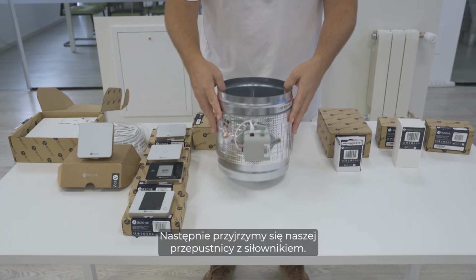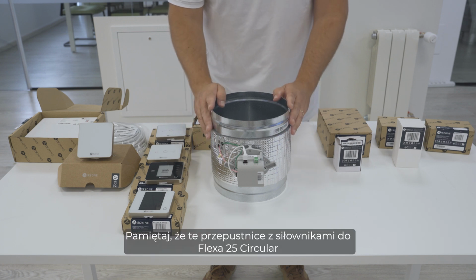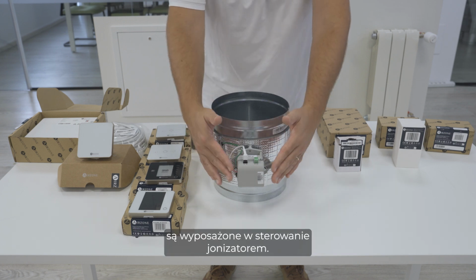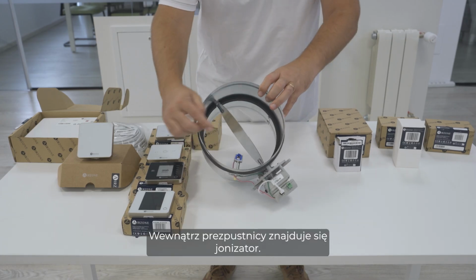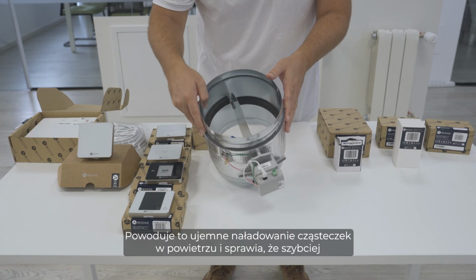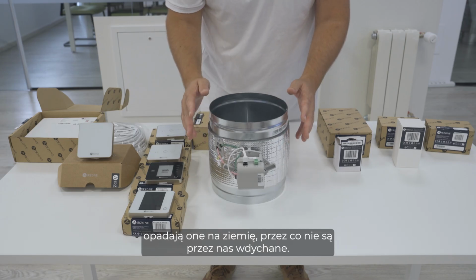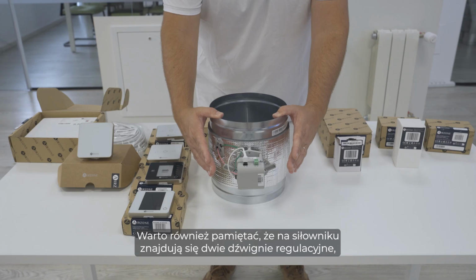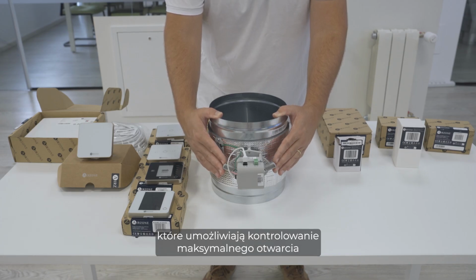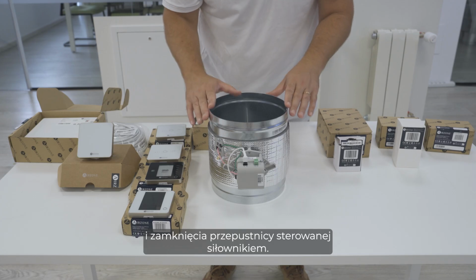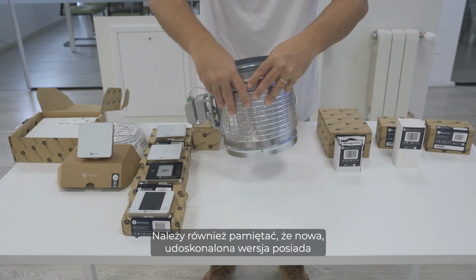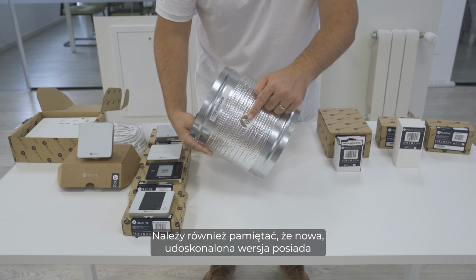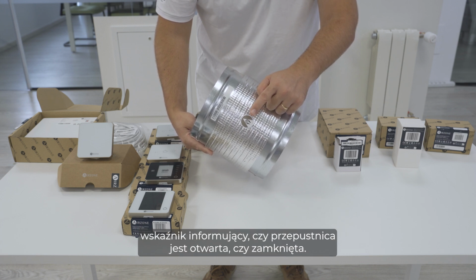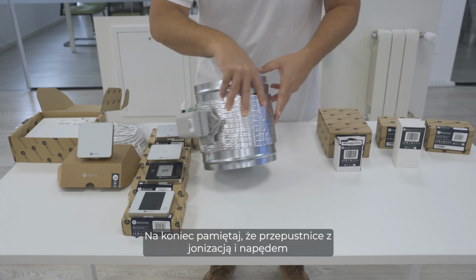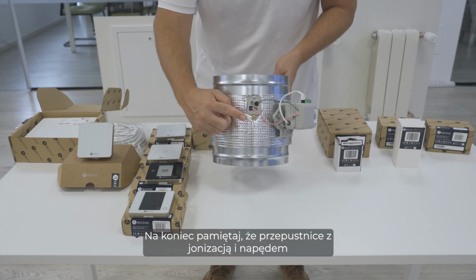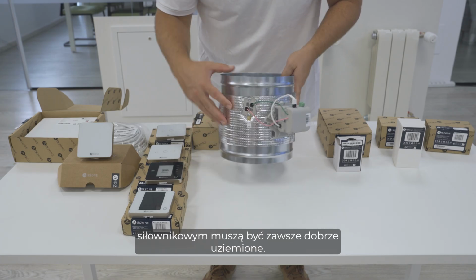Okay. Next, we're going to see our motorized damper. Remember that these motorized dampers for the Flexa 25 Circular come with the ionizer control. Within the damper itself, it's got the ionizer. This negatively charges the particles in the air and makes them fall to the ground quicker, so we do not breathe them. Also, remember that on the motor, we've got two regulation levers to be able to control the maximum opening and closing of the motorized damper. Also, we need to remember that the new updated version has got an indicator of whether the damper is open or closed. And finally, remember that the ionized motorized dampers always have to have a good earthing.